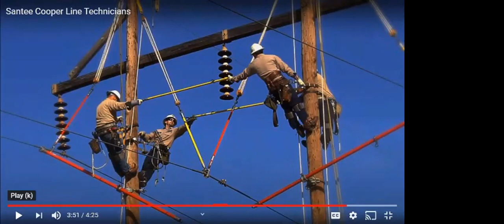It just gives you a good example. It's intricate work, definitely more time consuming. Obviously, by the rigging and everything going on here, that conductor is now out of the insulators and is being held up by two fiberglass sticks and two sets of what they call jacks or hoists. And what they're doing here is actually an insulator replacement. Those insulators are probably right around 100 pounds worth of insulators right there.